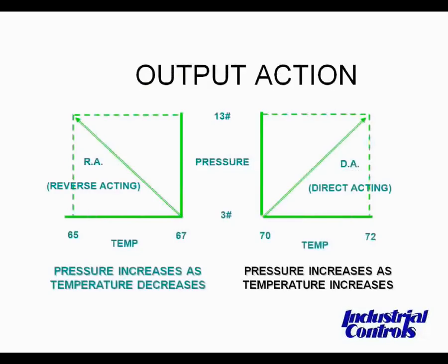Next, what we're going to talk about is output action. In any type of automatic control, we need to determine the control or action required. When using two-position control, the actions are pretty cut and dry. We would select a reverse-acting control if we want the system to increase its output energized state on a decrease in temperature and humidity. We would select a direct-acting control if we want the system to increase its output energized on an increase in temperature and humidity.